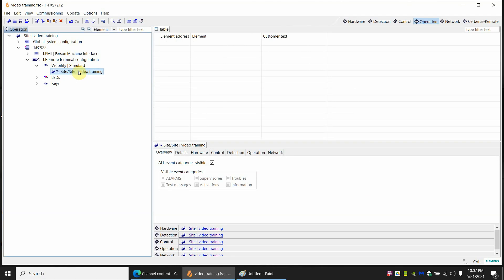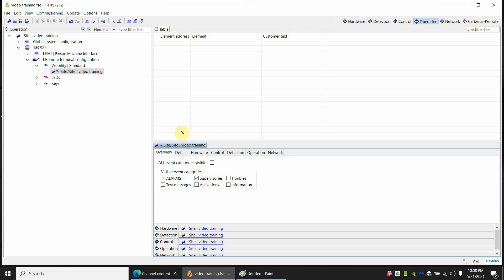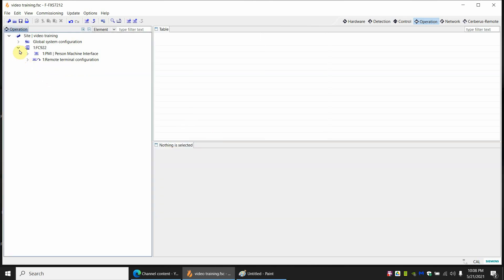So now the remote terminal is going to show the same thing as the panel. But let's just say this remote terminal we actually don't want to see everything. This is going to be kind of in a common area. We only want to see if there's alarms. If there's a trouble we don't want to show it on the enunciator, only on the main panel. So to hide the troubles on the enunciator by clicking on site you have an option right here that says all event categories visible. We're going to uncheck this. What do we want to see on here? We want to see alarms and show me supervisories. And that's it. Don't show me any troubles or activations or any information. Just these two things. Now our enunciator is only going to show us alarms and supervisories. If you want to change it this is where you would go. And that's your basic for an enunciator.